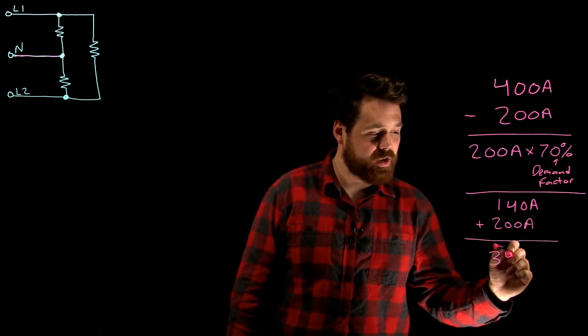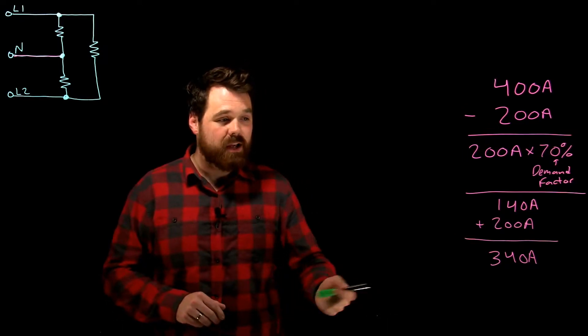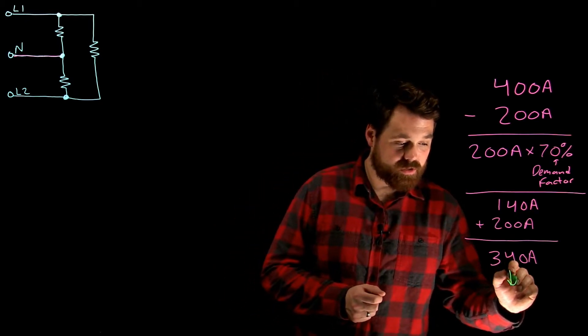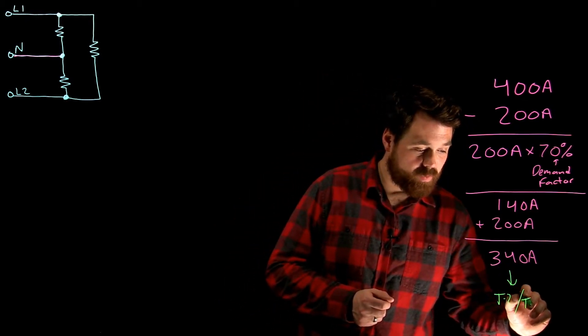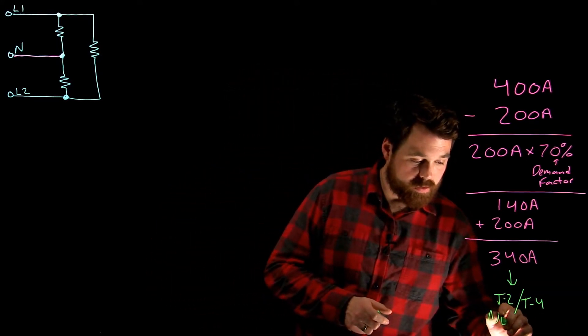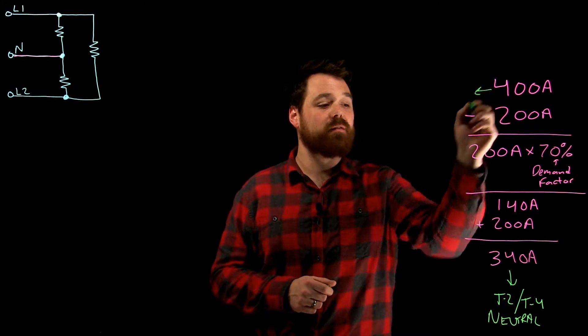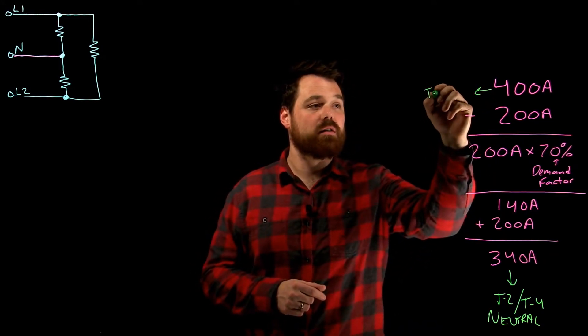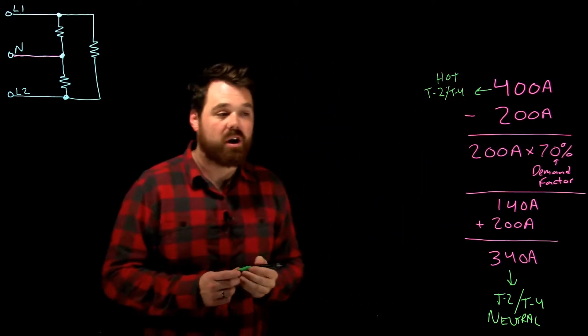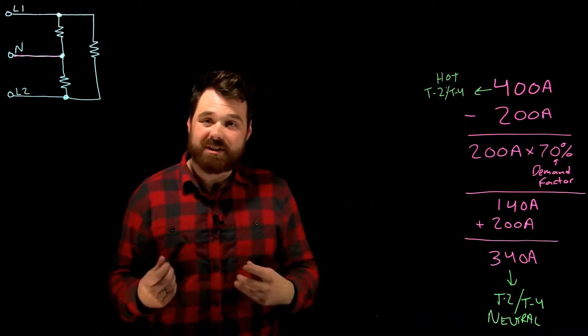In this case, it's going to give us 340 amps. Now this 340 amps becomes the required ampacity of our neutral conductor, meaning we are going to go to table 2 or table 4 to size our neutral conductor. But what we're going to need to do is we're actually going to take this 400 amps to size our hots or table 4. That's going to be to size our hots because our hots are going to take that, or our ungrounded conductors, and our grounded conductor is going to be sized based off of that.